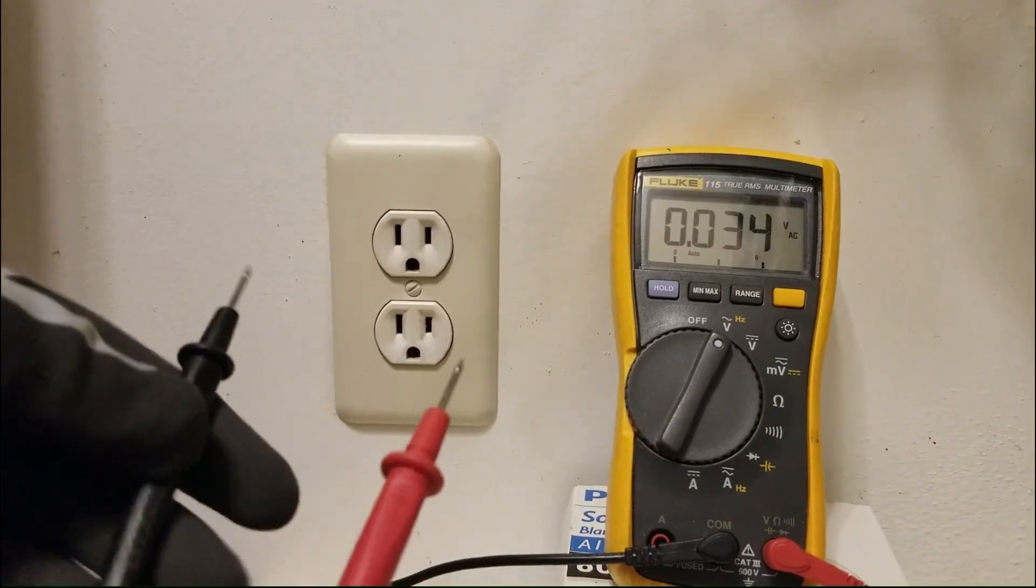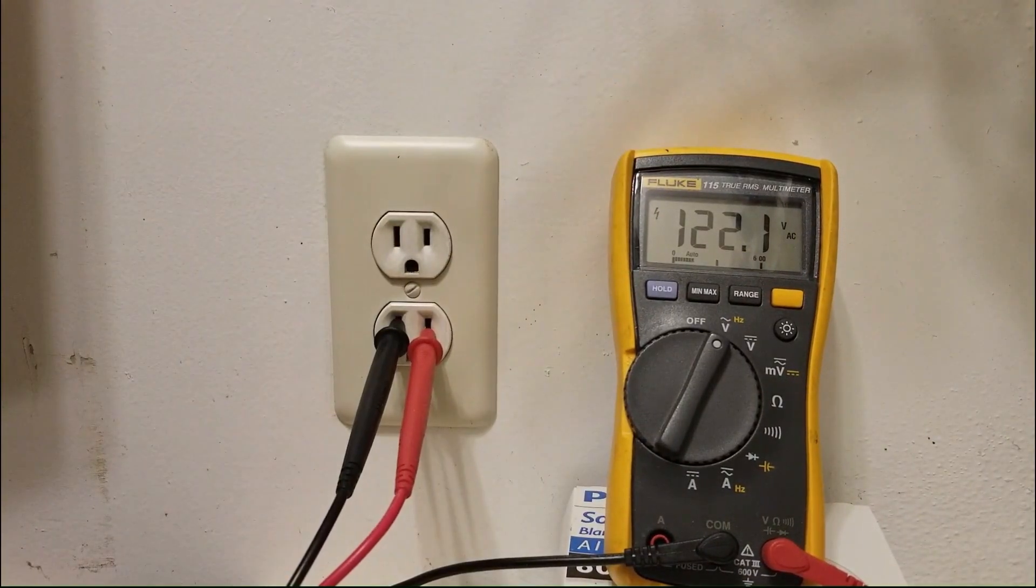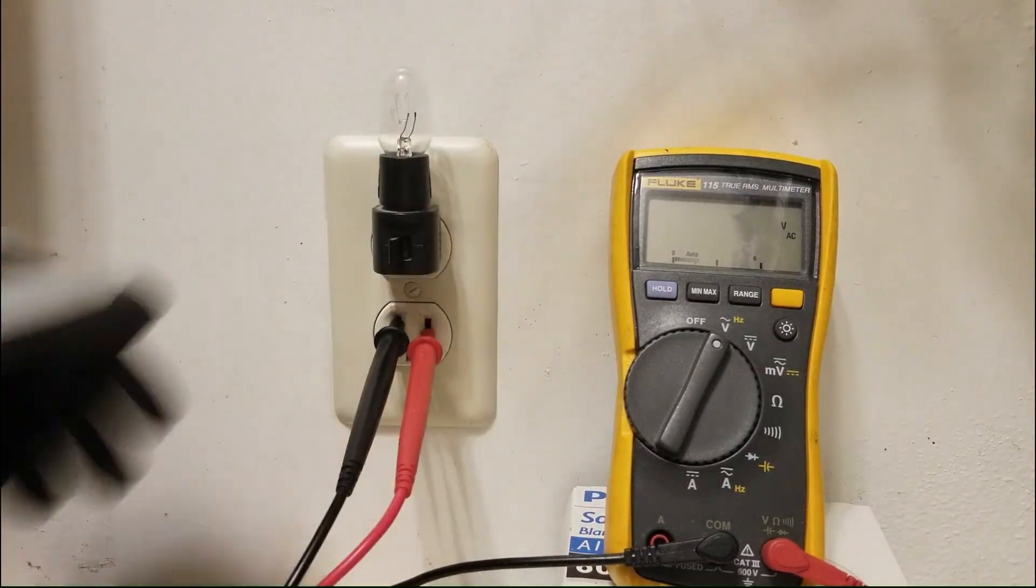In both cases the outlets measured fine using a traditional multimeter but when placed under any kind of load their voltages drop to unusable levels.